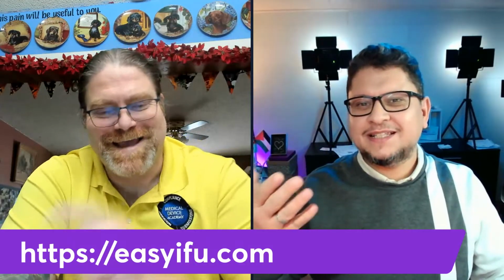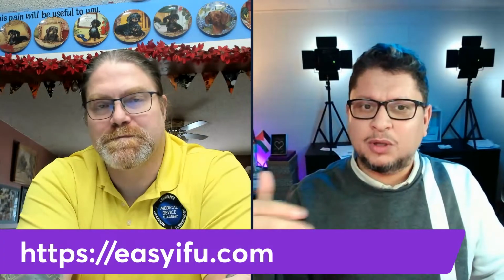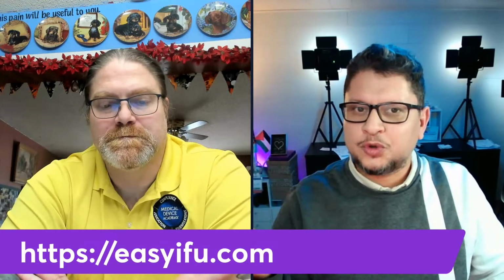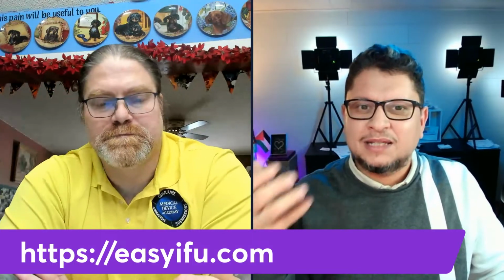Exactly. I mean, the checklist, and that's built into this, right? Exactly. So what we are doing now is that the checklist is specific for the EU MDR GSPR. So the GSPR is saying mainly what exactly you have to have there. But we are trying now to move also to the requirements for US, and for other regions, because we have also Australia, Japan, maybe Vietnam or Thailand, I remember, that are also asking for that. Brazil also asking for that.